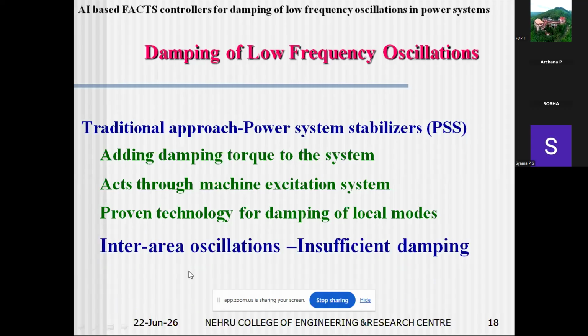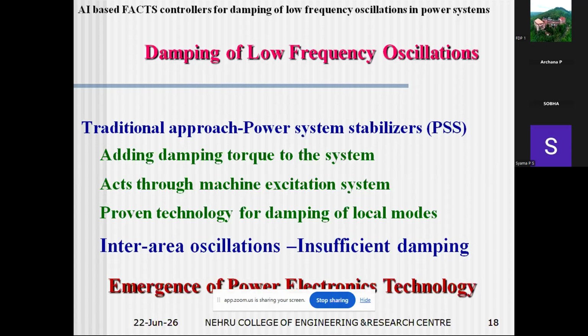But for inter-area oscillations, this may not always be sufficient. You will have to have more important methods. And similarly, I'll be coming to that, even in renewable rich systems where a lot of renewable penetration is there, again the conventional power system stabilizers will not work due to various reasons. I will be briefly touching those points. So this is where we have the emergence of power electronics technology. To address the inter-area oscillations, and to address the issues of renewable penetration into the system, if you want to add more damping torque to the system, you have to depend on power electronic technology.